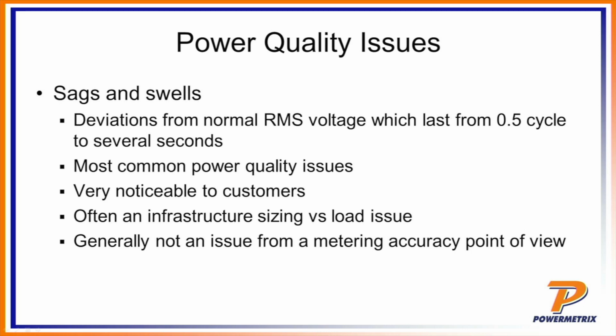My particular utility actually typically tends to run high. I was measuring the voltage the other day and I was recording upwards of about 128 volts coming out of my wall outlet. Now that's pretty darn high. Most electrical equipment, of course, is designed to accommodate a wide range of that, and we'll talk about what those ranges are in just a minute. But I will say this, a lot of times most equipment is more forgiving of a sag than a swell, meaning that if I have a dip in my voltage, a lot of equipment will ride through that. However, if I get a swell, I've gone through a lot of light bulbs with my particular utility just by the fact that they run a little bit higher than the typical voltage.